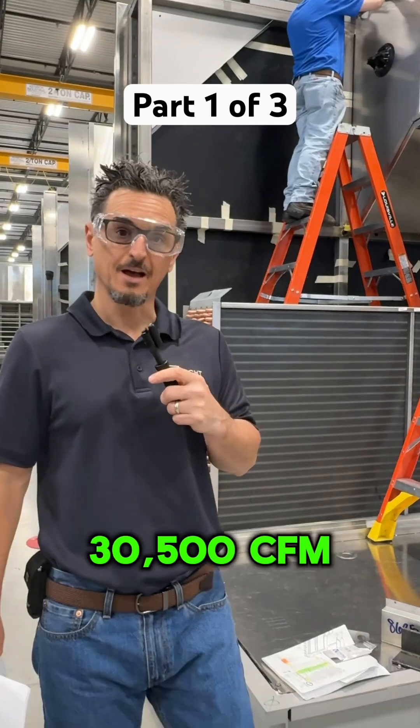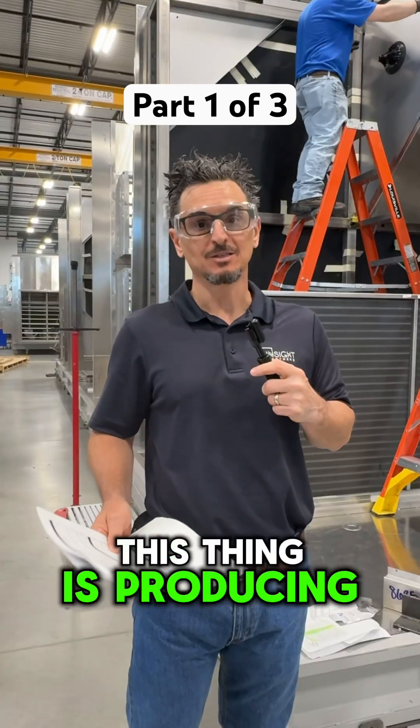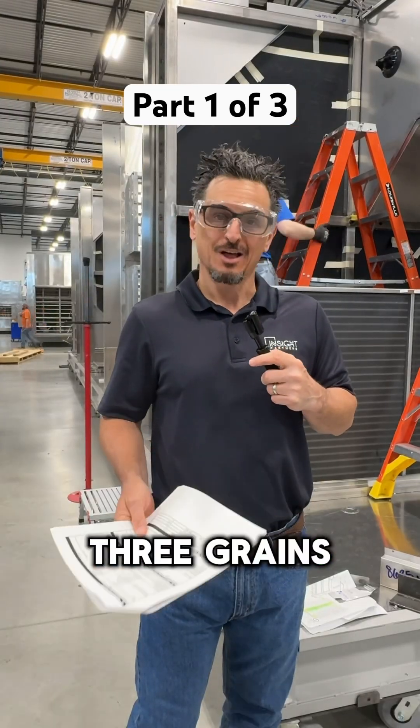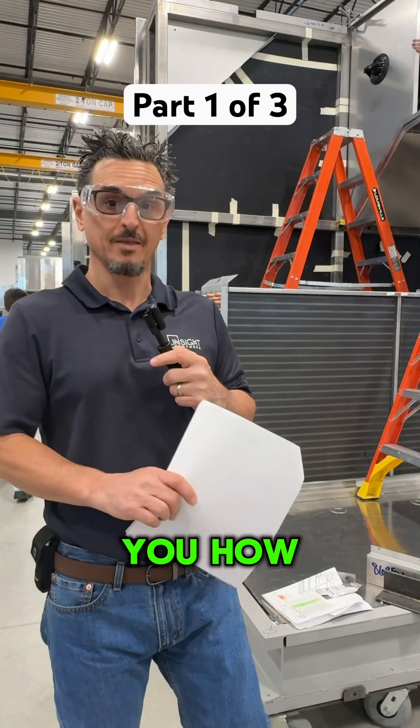We're going to do a walkthrough of a 30,500 CFM active desiccant unit. This thing is producing 3 grains on the leaving air side, so an extremely low dew point. Let me show you how that happens.